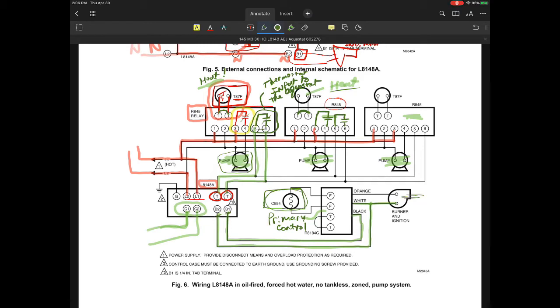It's imperative that those are isolated, because you certainly can't confuse the 120 volt circuit with the burner circuit, and between 5 and 6 is how you'd have to do that. So you have to really watch that. I'm going to label these here: this one's going to be number 1, this one's number 2, and this one's number 3. If any one of those, 1, 2, or 3, call, we complete the circuit here.